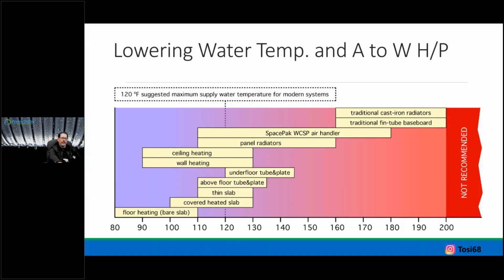This chart shows water temperatures required for our heating systems on a design day. That nice 120 degree line up the middle there. I'm not saying we can't pivot off of that under extreme conditions and go a little higher with air to water heat pumps.